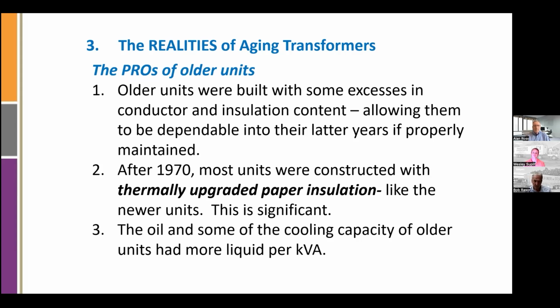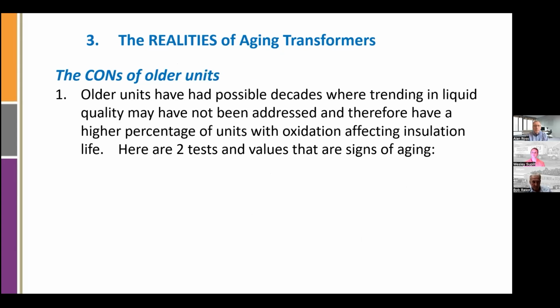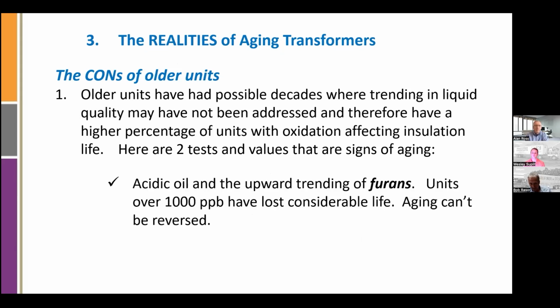The older transformers tend to create furans, a good indicator of knowing how the aging process of the insulation goes. That can tie directly to the remaining life in the transformer. Some more cons. Older transformers have decades of data. And there, again, is the furan comment, transformers over 1,000. Now, that's parts per billion. They've lost considerable life. And once you do lose the life through oxidation, through moisture, through overheating, you cannot restore it. So it's a good thing to keep up on it.